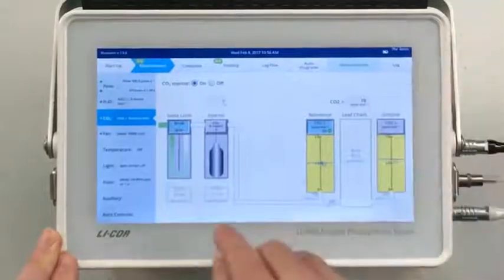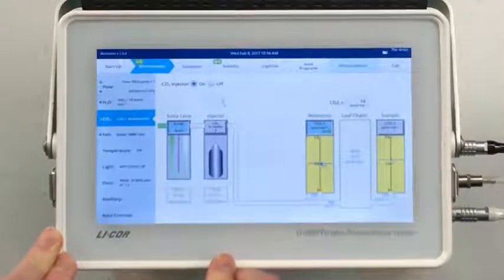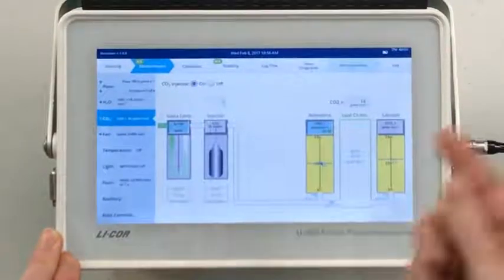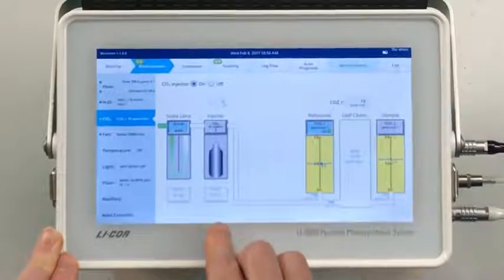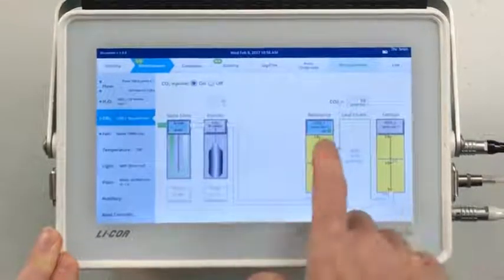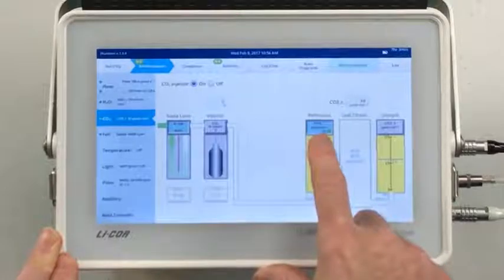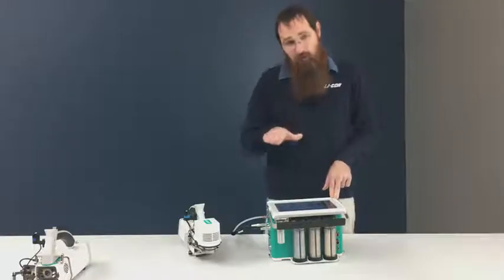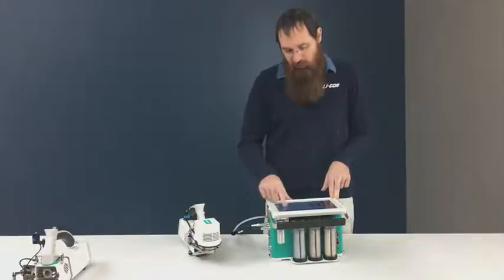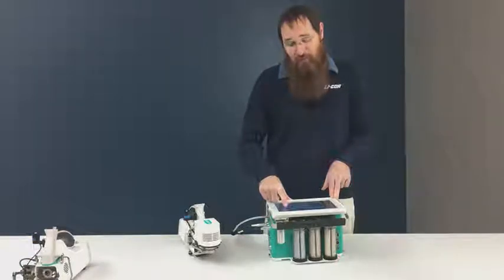So if I put a canister in here and I tap this to reset it, it's going to give me a count of how long that canister has been in there and been in use. Right now I'm controlling on my reference CO2 concentration, right? So that's like the concentration going into the chamber. And I've set it to 10 ppm.